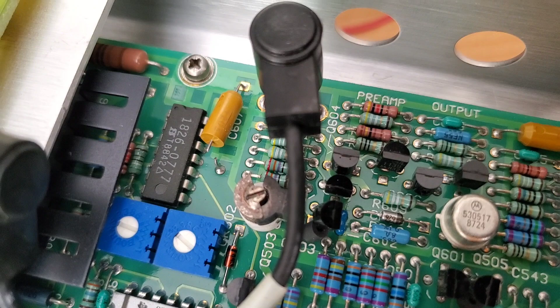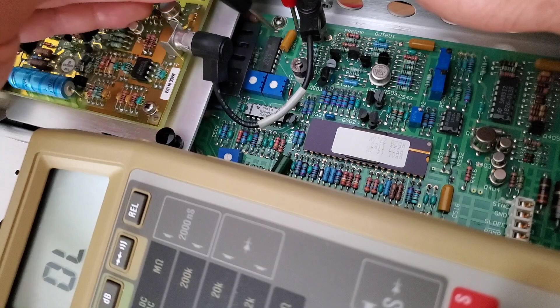So we're at the bottom board, the generator board, and that's the capacitor I cut one end of, which appears shorted. Let me put my digital meter up here so we can take a quick measurement. As we can see, it's shorted—again, no discoloration, no sign of damage, smoke, or sparks, but internally shorted.